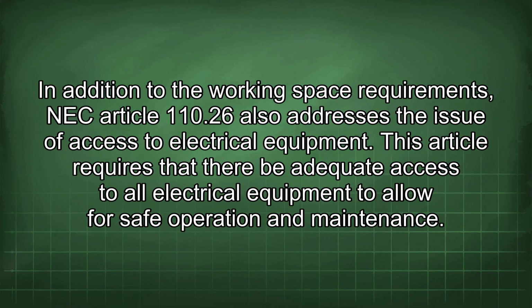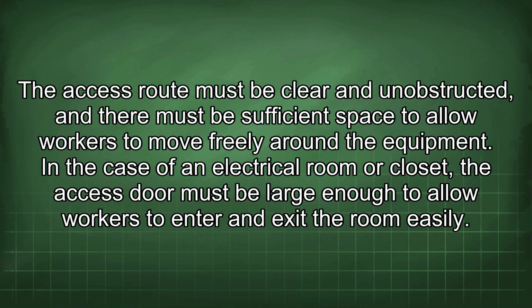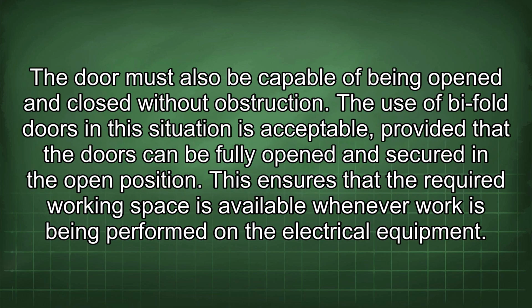In addition to the working space requirements, NEC Article 110.26 also addresses the issue of access to electrical equipment. This article requires that there be adequate access to all electrical equipment to allow for safe operation and maintenance. The access route must be clear and unobstructed, and there must be sufficient space to allow workers to move freely around the equipment. In the case of an electrical room or closet, the access door must be large enough to allow workers to enter and exit the room easily. The door must also be capable of being opened and closed without obstruction.